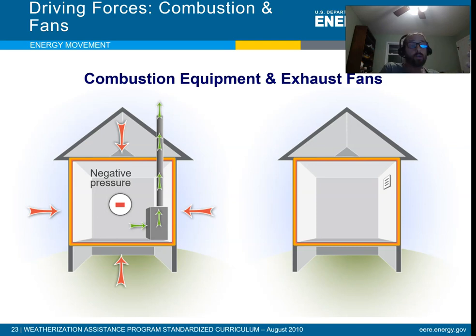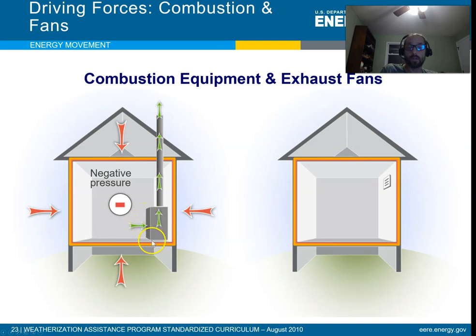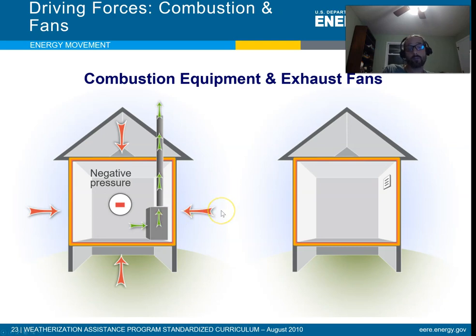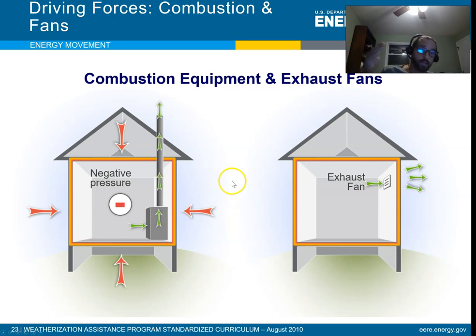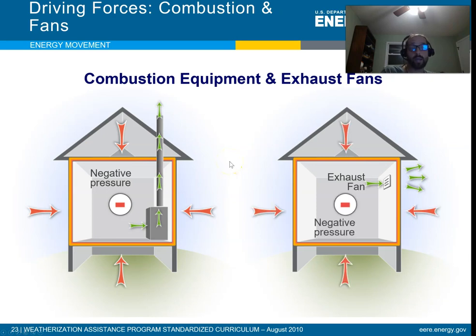Any time you move air out of a building, it's going to bring air in somewhere else — not necessarily right where the air is leaving. Standard furnaces pull air from inside the house and dump it out, which means outside air is pulled in as well. You can get around this with direct combustion, which pulls air from outside to feed the combustion reaction — that's an advanced high-efficiency measure.